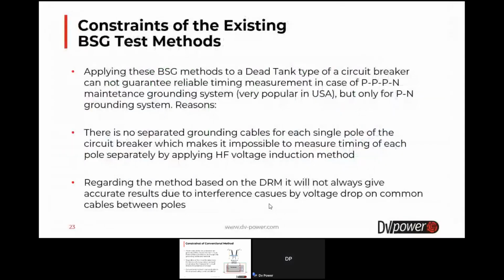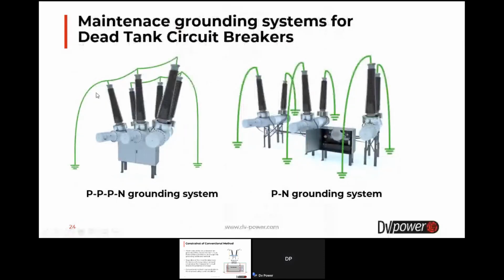Regarding the method based on dynamic resistance measurement, it will not always give accurate results due to interference caused by the voltage drop on the common cables between poles. When the dynamic resistance measurement is applied, there will be current through the main contacts as well as through the grounding contacts, but also through the common cables connecting terminals from one side of the circuit breakers. That current will cause voltage drops, which can then cause unreliable detection of the arcing contacts touch or separation.